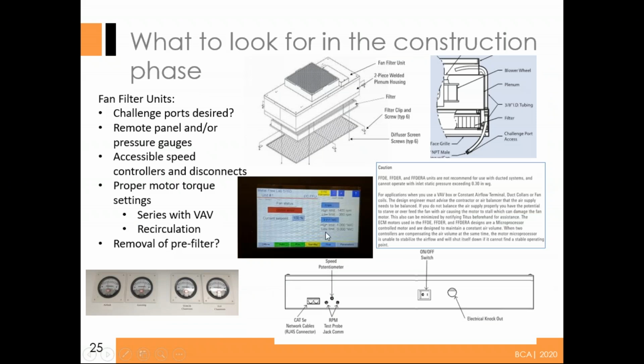Here are some fan filter units, just a couple of things that we like to look at. This will come up in the future, but challenge ports are basically how the certifier is going to test it. They spray an aerosol into the hood, but they have to have access to the upstream side of the filter. So there's this little challenge port that you can get from the factory. Some users like to see these remote control panels.